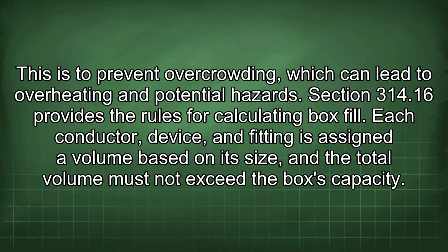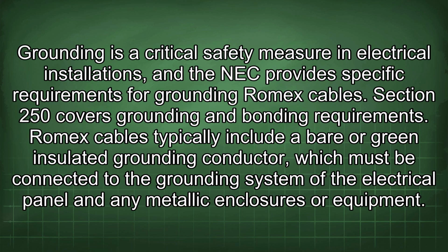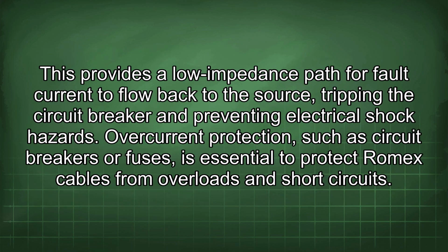Grounding is a critical safety measure in electrical installations, and the NEC provides specific requirements for grounding Romex cables. Section 250 covers grounding and bonding requirements. Romex cables typically include a bare or green insulated grounding conductor, which must be connected to the grounding system of the electrical panel and any metallic enclosures or equipment.